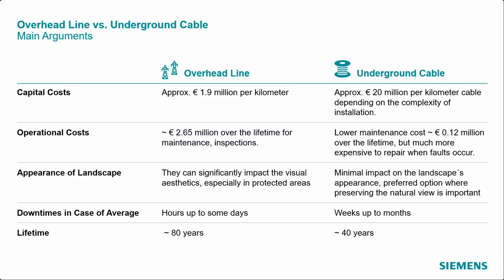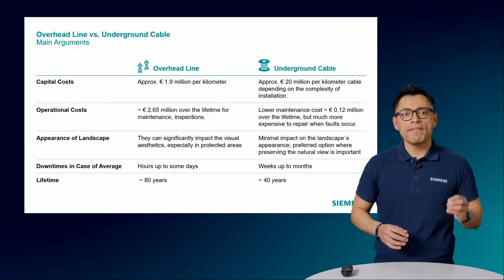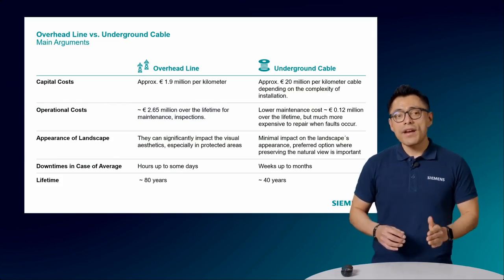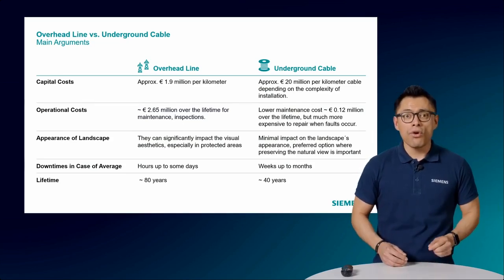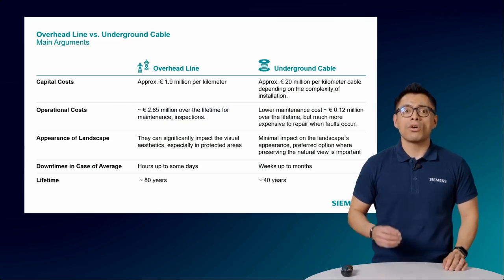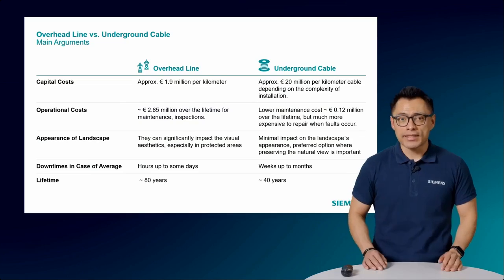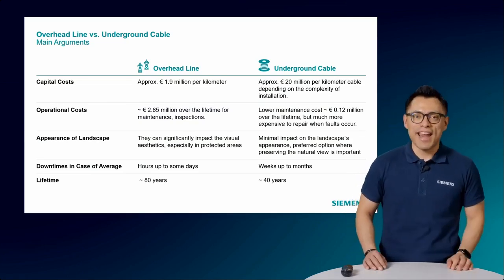Overhead lines have a higher operational cost for maintenance during their lifetime as they are exposed to open air. However, they have the advantage that when a fault occurs, it is relatively easy to localize and repair. In comparison, the operational cost for underground cables is lower as they are protected by the infrastructure underground. However, repairs due to faults can result in very expensive costs due to the materials, machinery, and challenging civil works. The visual impact of overhead lines may face opposition in scenic or urban areas. Therefore, they are highly used for long distances in rural areas or in areas with less population density. Underground cables have, in comparison, a minor visual impact, which makes them suitable for urban or densely populated areas.